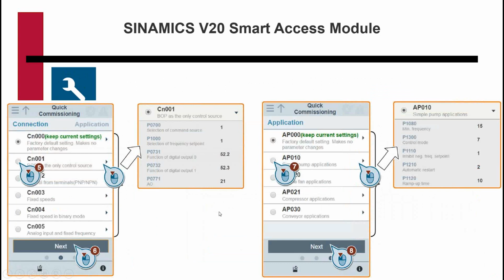So next steps in the V20 quick commissioning, you've got some macros to choose from. There's several different macros available. Cn is going to be your connection type, or how your I/O is connected, and then your application is going to be, what type of motor application are you doing? Is it a pump? There's fan, compressor, or conveyor. These just populate some parameters in the drive based on those settings.